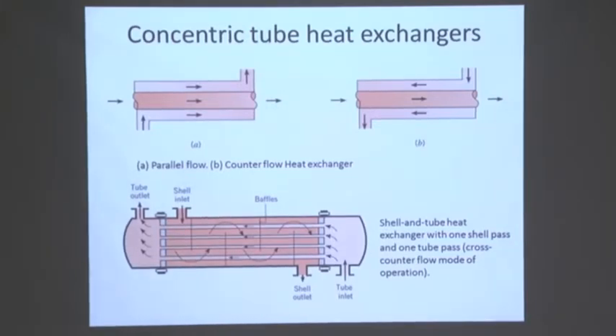And this way, if you divide the flow and make hurdles by putting these walls, these are known as baffle walls or baffles - you can have a cross flow and counter flow type combined. When it flows in this direction through this baffle, it is a cross flow. Again, it is also a counter flow. So therefore, it is a mix of cross counter flow mode of operation.